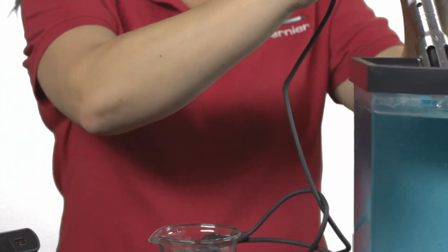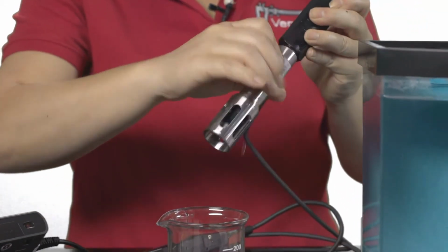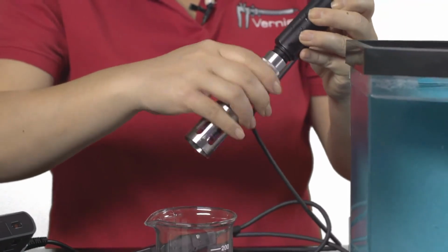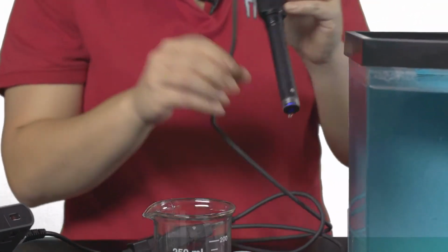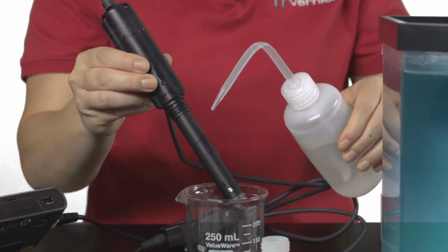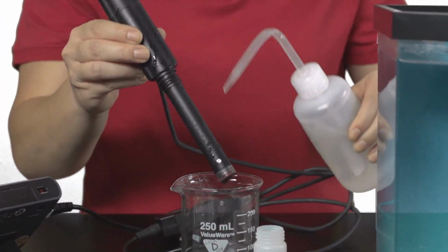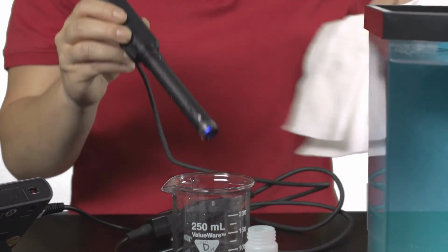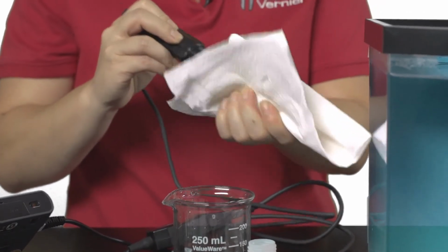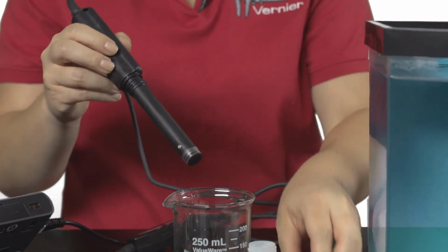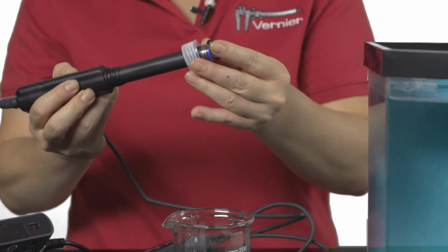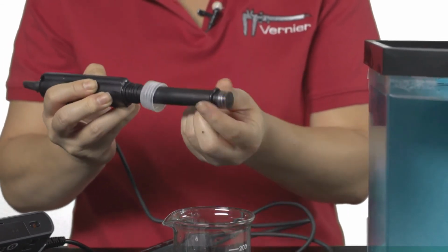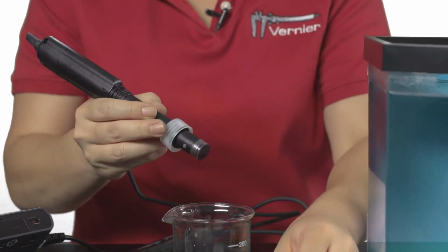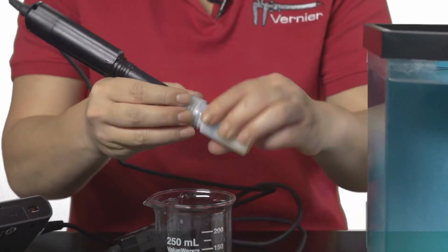When you have finished using the optical DO probe, rinse the tip with distilled water and gently blot dry. Place the optical DO probe back into the storage bottle. And tighten.